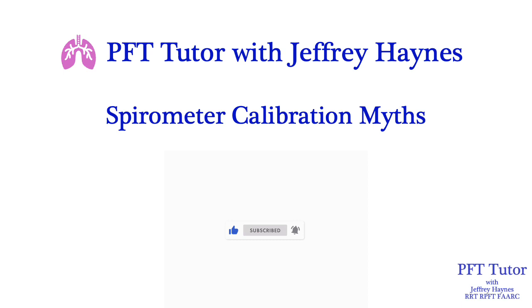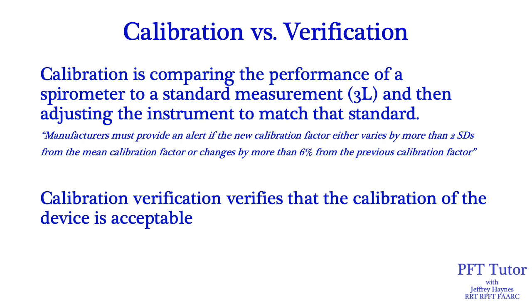Most technologists refer solely to calibration, but calibration is not what you are doing with your 3-liter syringe first thing in the morning. In most cases, you are actually performing verification. Calibration and verification are very different things, and it's important to recognize the difference. Calibration is comparing the performance of a spirometer to a standard measurement — in this case 3 liters — then adjusting the instrument to match that standard.